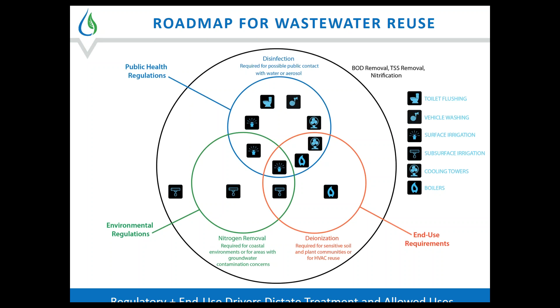So public health regulations weigh in, and disinfection is required, as mentioned before, for public contact applications. In certain areas, environmental regulations also apply for disposal to the environment, for removal of nitrogen and/or phosphorus. But even if you meet both environmental regulations and public health regulations, the water may not be fit for use in certain applications based on cooling equipment, boilers, or soil conditions. And so deionization or RO is required in those situations. Next slide.